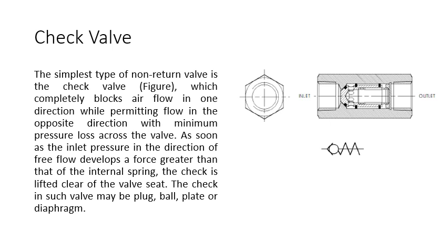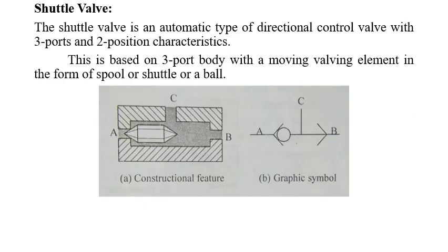The check valve has a spring-loaded moving component that allows fluid to flow in only one direction, completely blocking air flow in the other direction while permitting flow in the opposite direction with minimum pressure loss across the valve. As soon as the inlet pressure in the direction of free flow develops a force greater than the internal spring, the check is lifted clear of the valve seat. The check in such valves may be a plug, ball, plate, or diaphragm type.